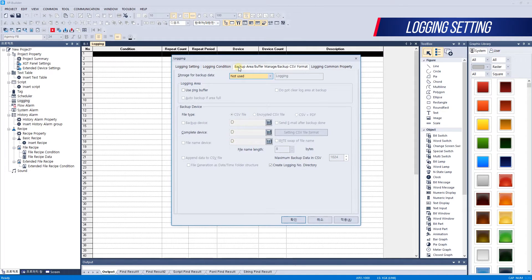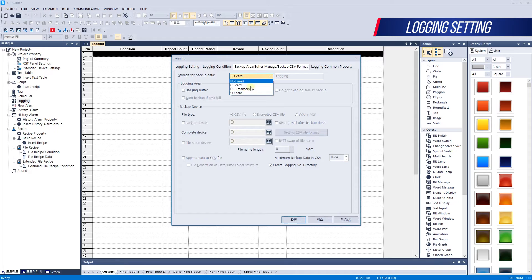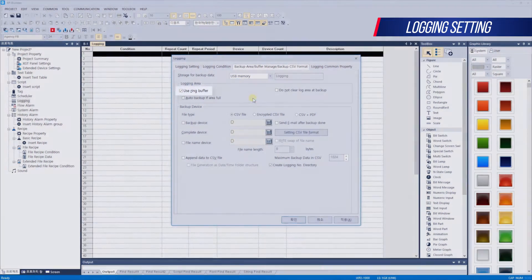Next, let's set backup area and buffer management. By default, logged data is stored in NVRAM inside HMI. Once logging backup is enabled, data in NVRAM can be backed up to external storage devices as CSV and PDF files. Backup data is saved to CF card, USB memory, and SD card, though it may vary by HMI model. If you check use ring buffer, it overwrites logging data when the storage area is full. If you check auto backup when area is all used up, it saves data automatically to the specified storage medium when the logging area is all used up. This cannot be used in duplicate with use ring buffer.